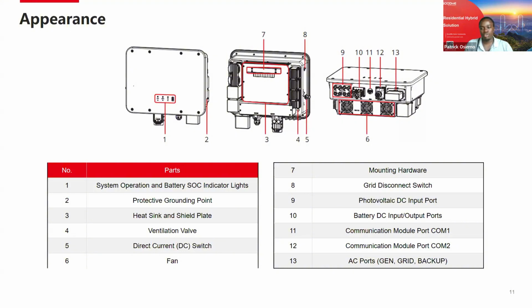And at the bottom is where you'll see the fans and the connection ports for the PV strings, for the battery communication cable, and also for the AC ports. The inverter has 3 AC ports. One port is for the generator, the other port is for the grid, and we have another port for the backup, that is, the critical loads.